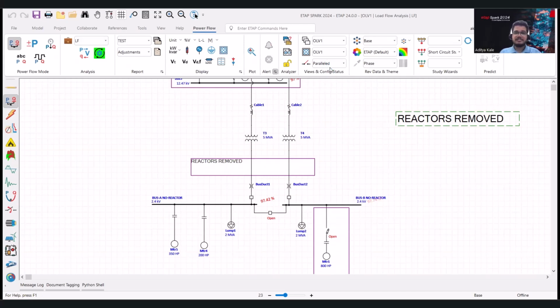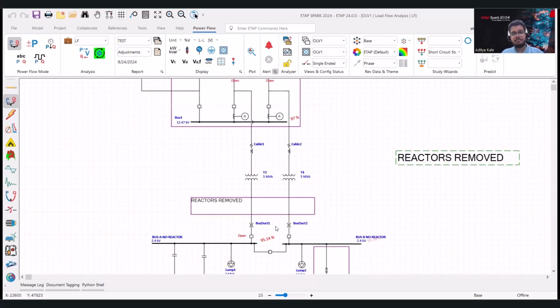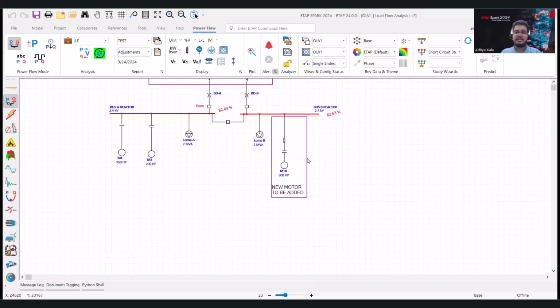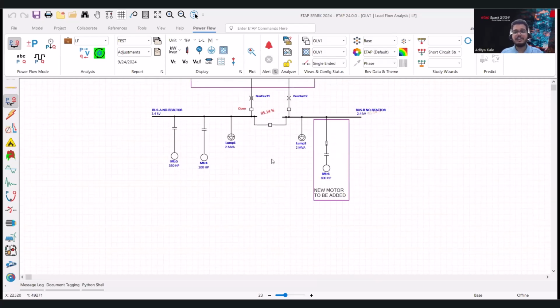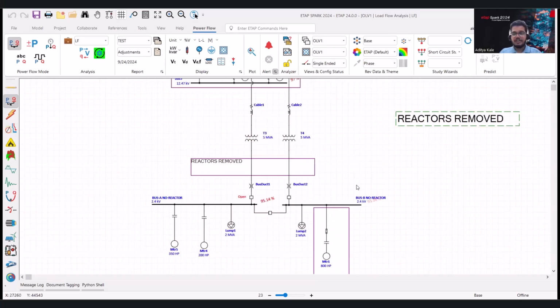For the paralleled, it is the same. And let's take a look at the worst case single-ended scenario. We have a motor bus starting voltage of 95%. That is a tremendous improvement over 82% voltage. Now we have about 95% voltage. So the motor can be successfully started even with a 15% voltage drop during acceleration. The contactors are safe and we would not have any nuisance trip. So we can successfully start the motor based on the voltage evaluation itself.